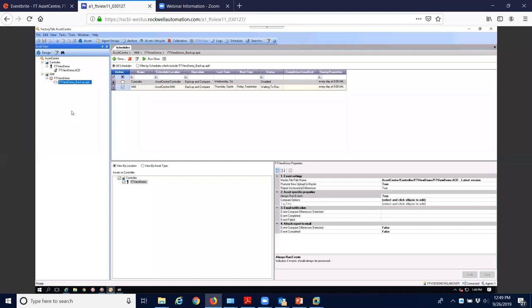So if you take it from a 4.0 to a 4.1 version and replace everything, it will automatically replace everything, and as long as the points don't change on the HMI side, all of that will still work. What you have to do is make sure that you're matching the 4.1 image set on the controller to the 4.1 faceplates on the HMI, so that you don't have any wireframing issues and things of that nature. It can be done. I would not recommend it, but it can be done.